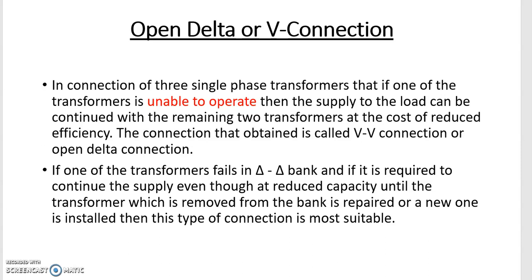Such connection is usually employed when three phase load is comparatively small, so that installation does not warrant three phase bank, or else one of the transformers in a delta-delta bank fails. The other reason can be it is anticipated that future load will increase to warrant the closing of open-delta at some later date.